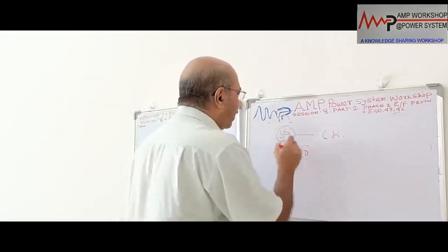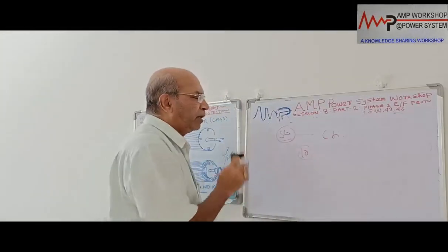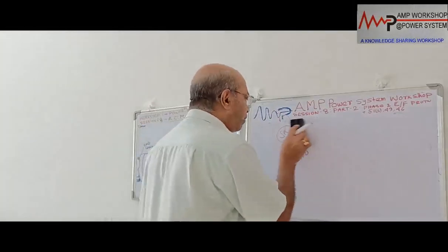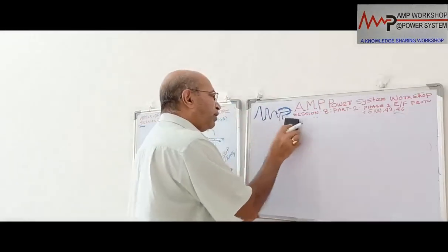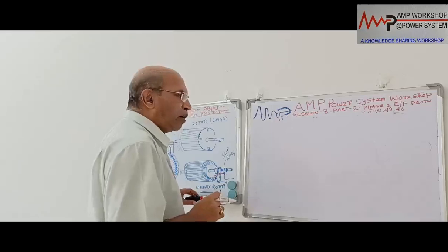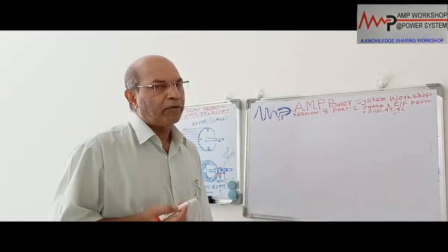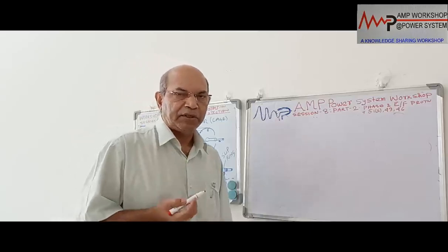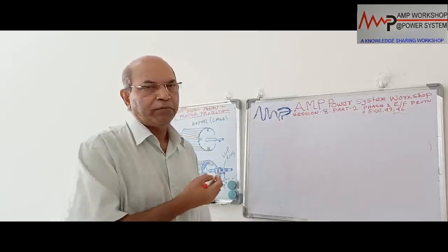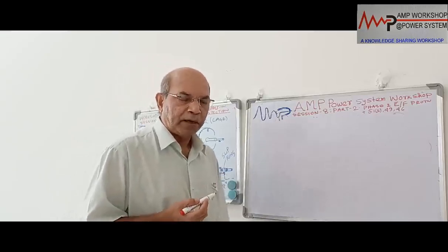But this type of fault current should be fed from the upstream. If the system does not have that capacity, then this 50 relay will not operate. So 50 relay application is limited. If the upstream has enough capacity, then we provide 50 relay, the instantaneous overcurrent relay, and it will operate immediately. But in most cases where we connect the motor, the upstream has the capacity to feed the motor, because most motors we start DOL, so it has enough capacity to feed the power.